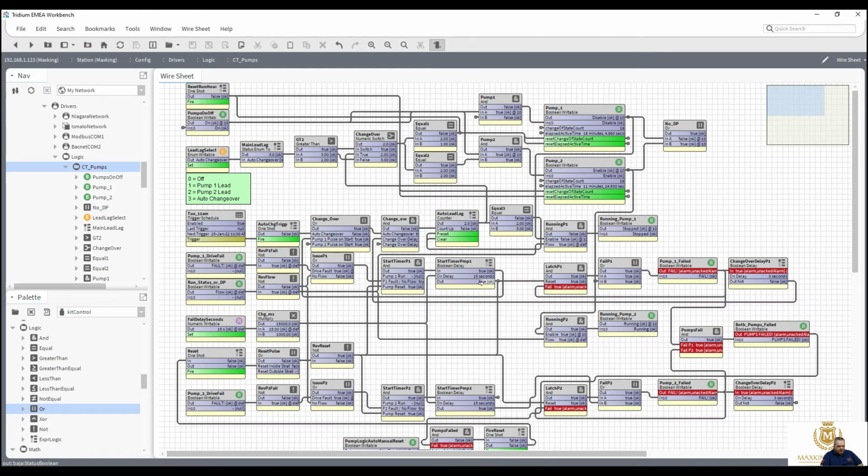So that's both pumps failed, both are in alarm, yet we're still enabled on that pump. That pump is still giving me a 2, which we really don't want. We want to switch them pumps off because they've both failed. Mind you, we've got a DP still.